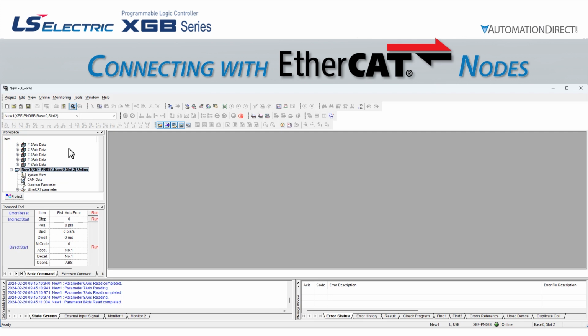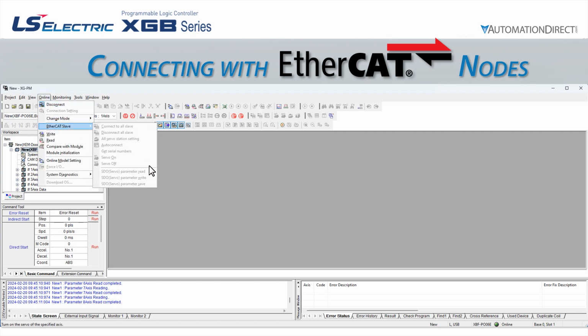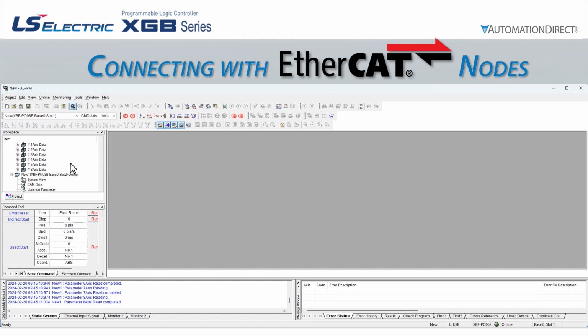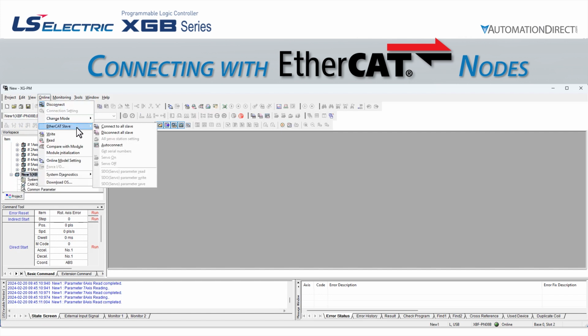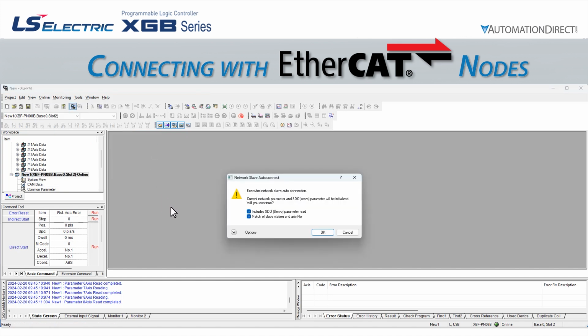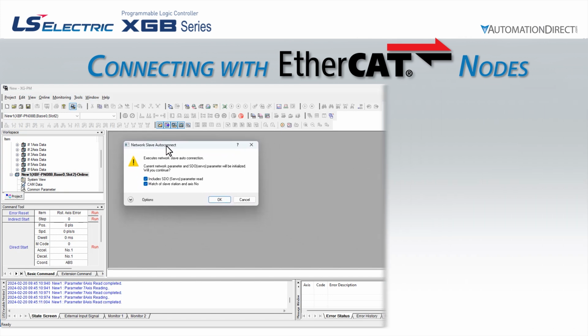To do this, we need to have the PN08B module selected in the project window. If we have selected the onboard step and direction motion controller, this next step will be grayed out. Once we have the proper selection in the project window, we can go to Online, EtherCAT Slave. We see that we have options to connect to all slaves, disconnect to all slaves, and autoconnect. We will select AutoConnect. This opens the Network Slave AutoConnect pop-up window.